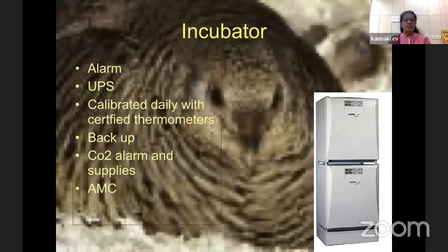But of course, never start off with a single incubator. Must have minimum 2 incubators. Having a bench top is also equally good. And they are stackable also. So all can be stacked in one area. Space occupied is less. And the CO2 alarm, CO2 is again important. Time your supply, CO2 supplies. And when connected, when the CO2 falls, you should be having an alarm system to notify that.